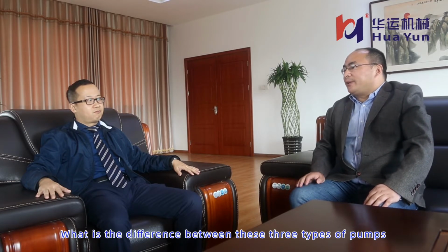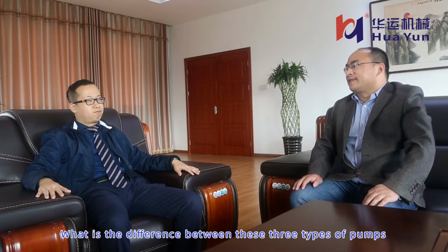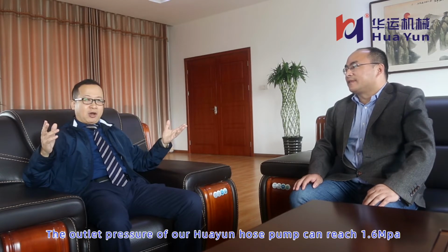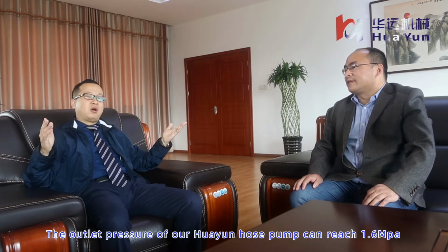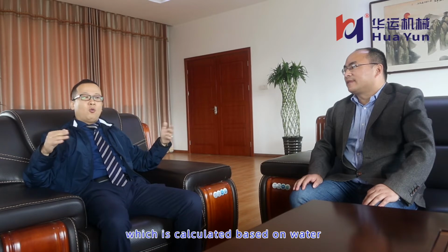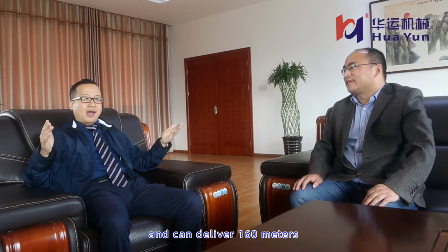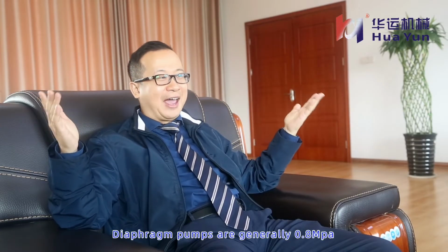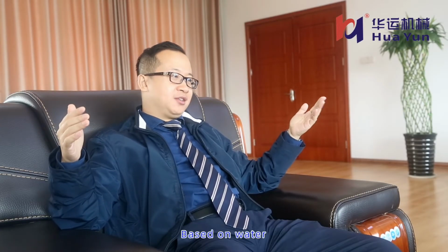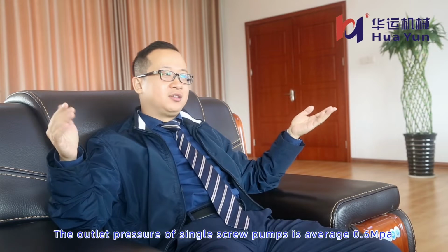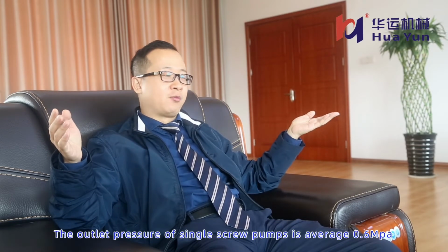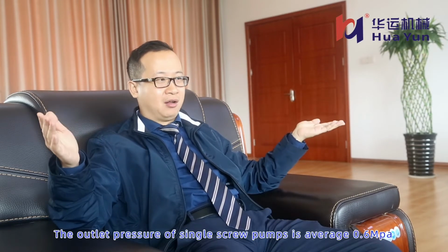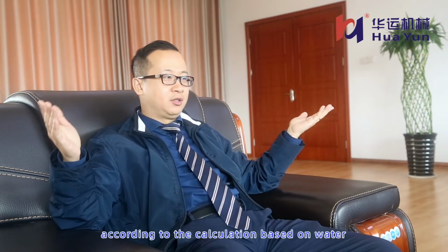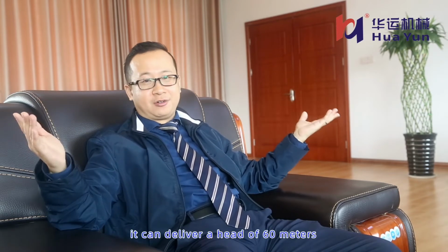What is the difference between these three types of pumps? The outlet pressure of our Huayun hose pump can reach 1.6 MPa, calculated based on water, and can deliver 160 meters. Diaphragm pumps are generally 0.8 MPa, based on water, and can deliver 80 meters. The outlet pressure of a single screw pump is on average 0.6 MPa. Calculated based on water, it can deliver a height of 60 meters.